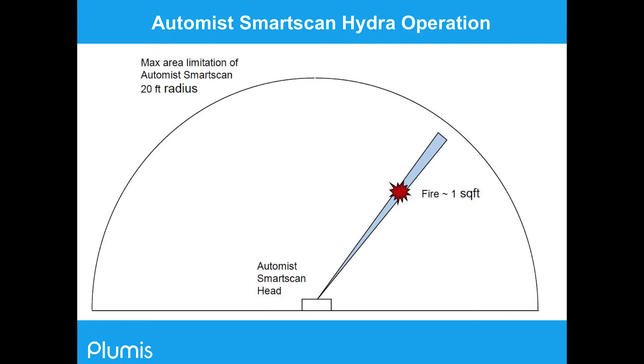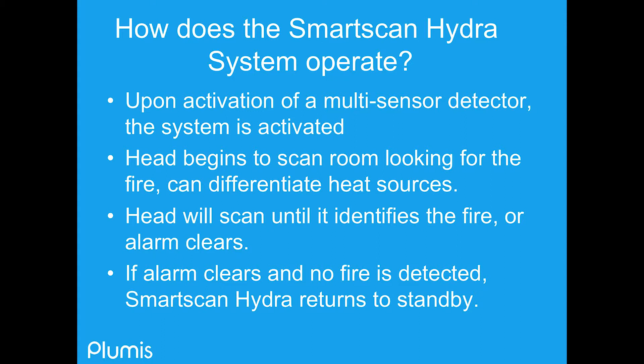So how do we work? Basically, we use a multi-sensor detector, and so that is going to be a photoelectric smoke alarm, plus a heat detector, which is both fixed temperature at 135 degrees, which is standard in the industry, and a rate of rise. Why do we do that? Because you have different kinds of fires, especially in the residential world. You may have a smoldering fire, or you may have a pretty aggressive fire. Both of those sensors take into account both of those issues. The head begins to scan the room, looking for the fire. It'll scan until it identifies the fire, or the alarm clears. So if it does not see the fire and the alarm clears, it will go back into the standby mode and not disperse water mist.